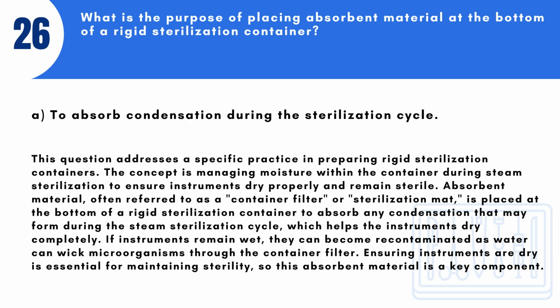Absorbent material, often referred to as a container filter or sterilization mat, is placed at the bottom of a rigid sterilization container to absorb any condensation that may form during the steam sterilization cycle, which helps the instruments dry completely. If instruments remain wet, they can become recontaminated as water can wick microorganisms through the container filter. Ensuring instruments are dry is essential for maintaining sterility, so this absorbent material is a key component.